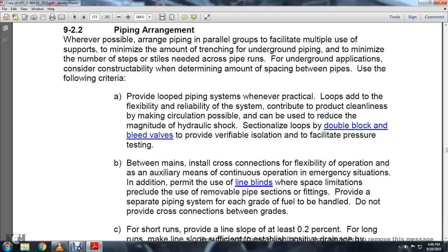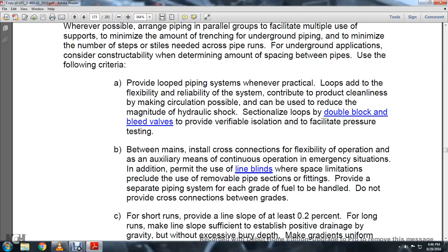Additionally, permit the use of line blinds where space limitations preclude the use of removable pipe sections or fittings. Provide a separate piping system for each grade of fuel to be handled. Do not provide cross connections between grades.